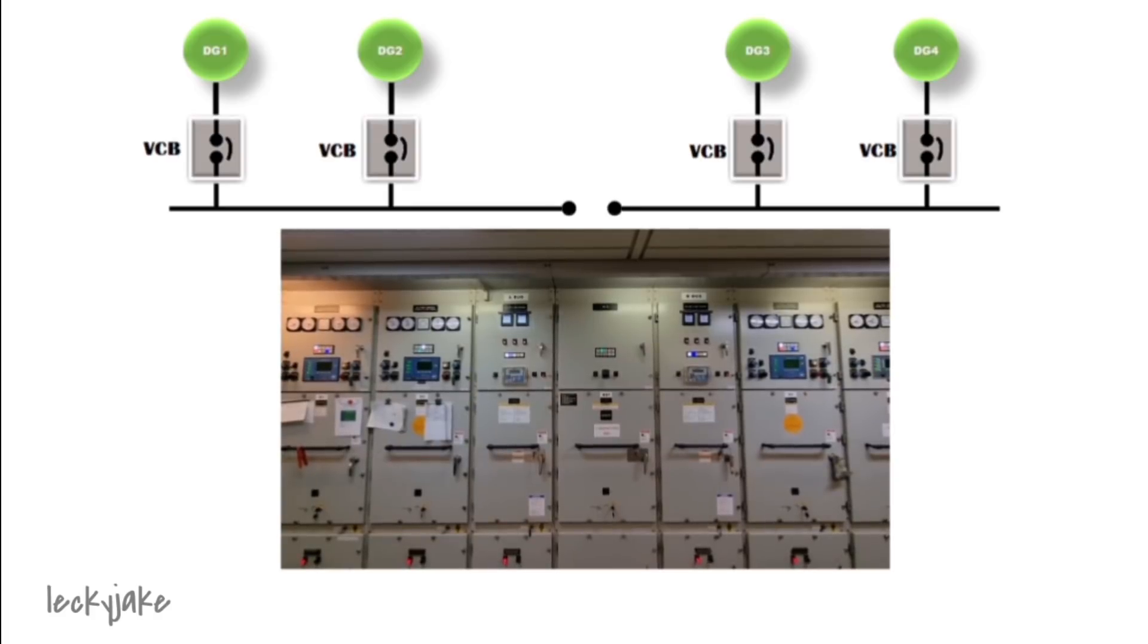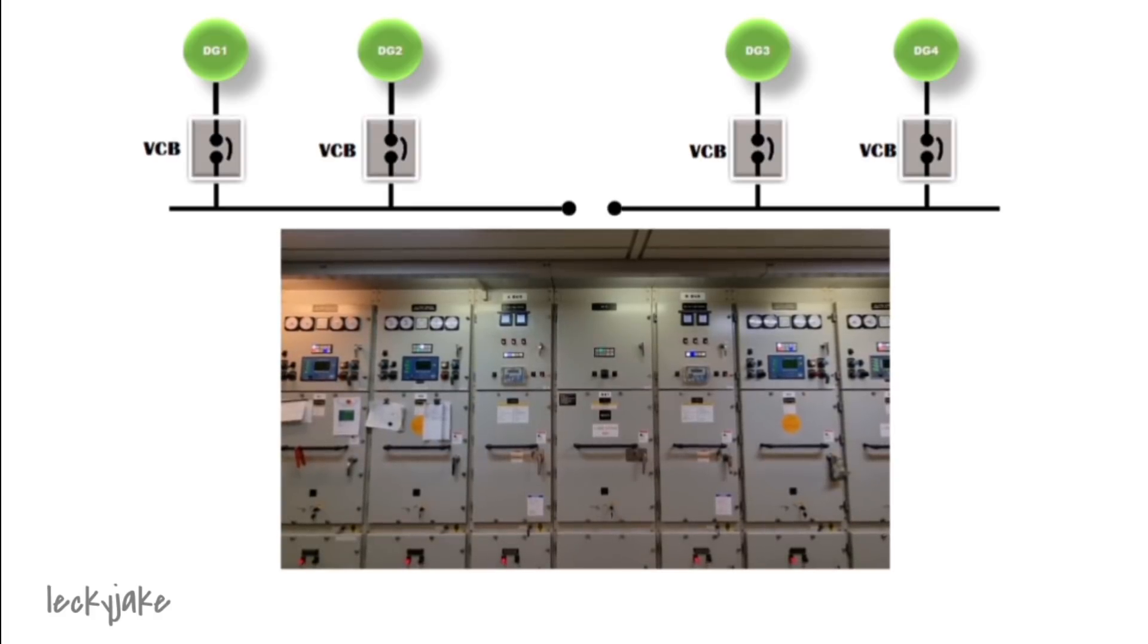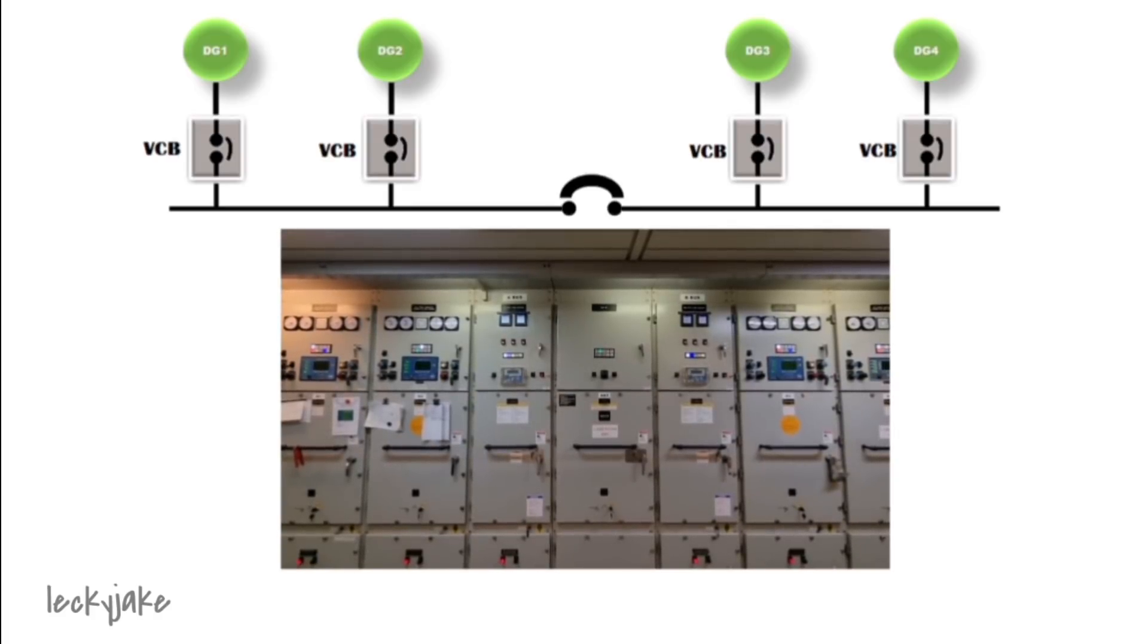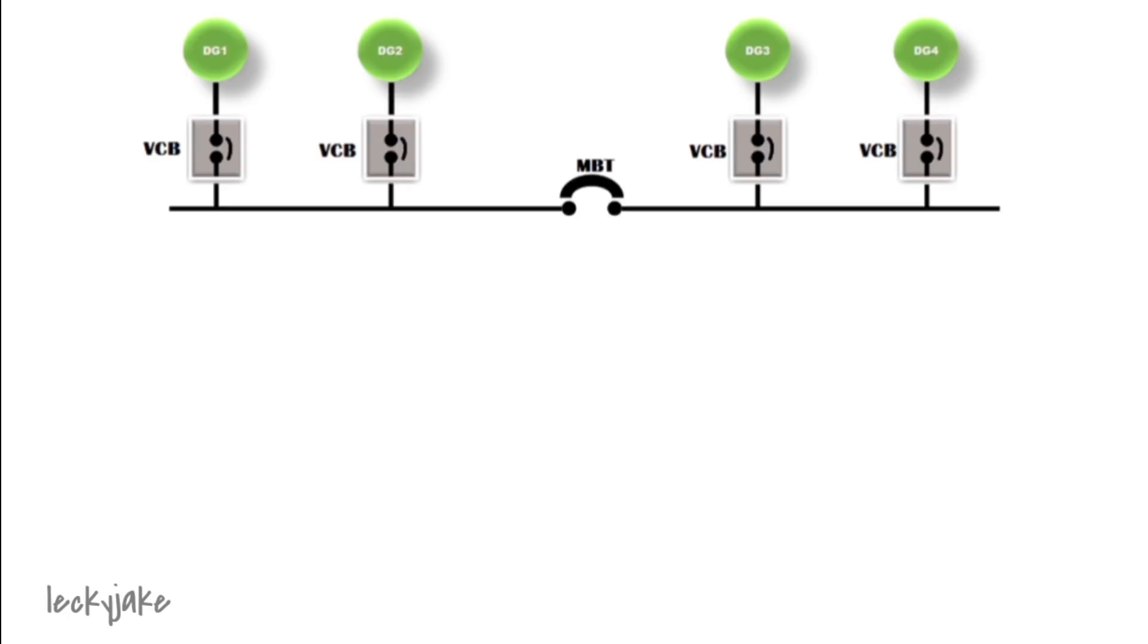But the bus bar is separated into two groups, the bus bar A and B which is being separated by a main bus tie. The main bus tie is a vacuum circuit breaker which is normally closed. The function of this main bus tie is to have a separation between these groups so that we can still service the other part of the main switchboard whenever required.